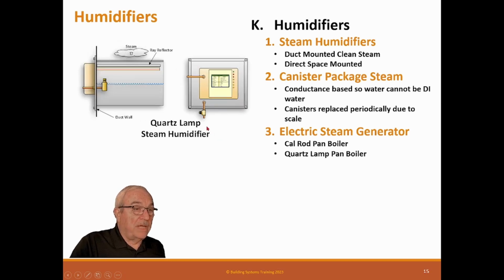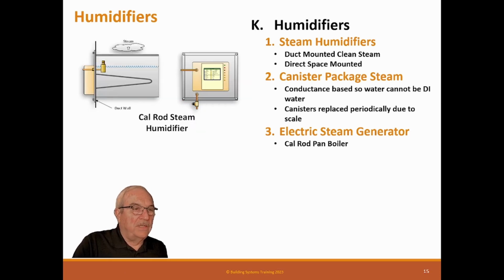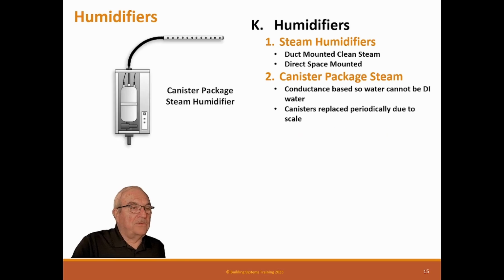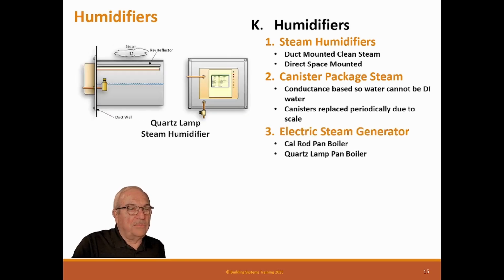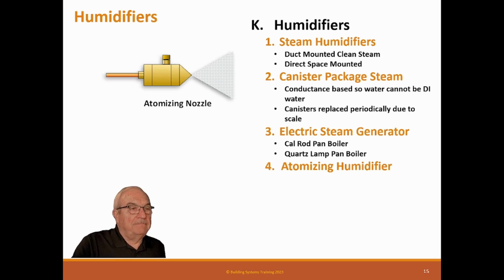We have a quartz lamp one, which is exactly the same, except it has a quartz lamp and a shield, and it heats the surface of the water, same thing. The problem with these two, though, is scale. The scale causes these to scale up, and boy, they have huge maintenance problems to take care of. So both of these are not too popular, to tell you the truth. Canister is what normally happens, because these are such maintenance issues to deal with.